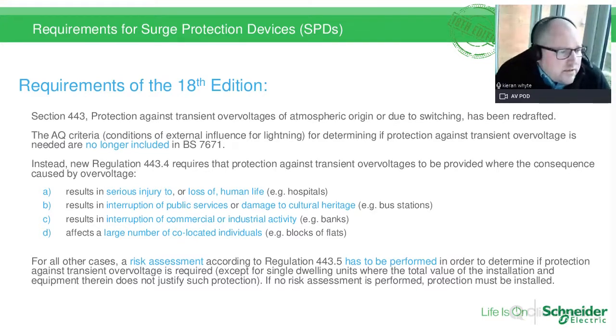443.4, requires protection against transient overvoltages to be provided where the consequence caused by an overvoltage results in serious injury to or loss of human life, results in interruption of public services or damage to cultural heritage, results in interruption of commercial or industrial activity, or affects a large number of co-located individuals, e.g. a block of flats. For all other cases, a risk assessment according to regulation 443.5 has to be performed in order to determine if protection against transient overvoltage is required, except for single dwellings.